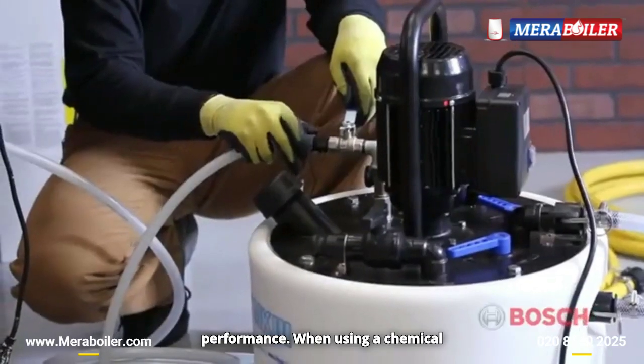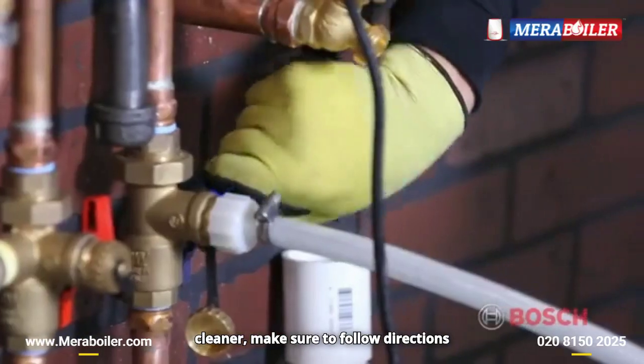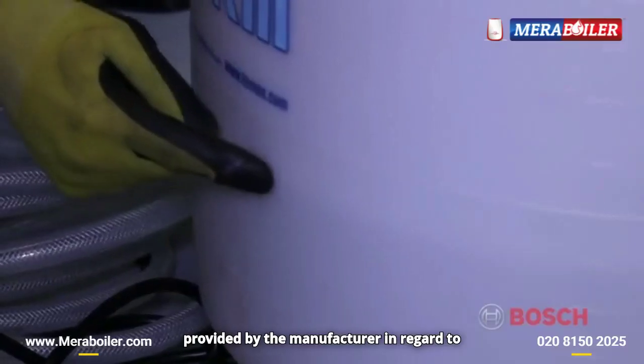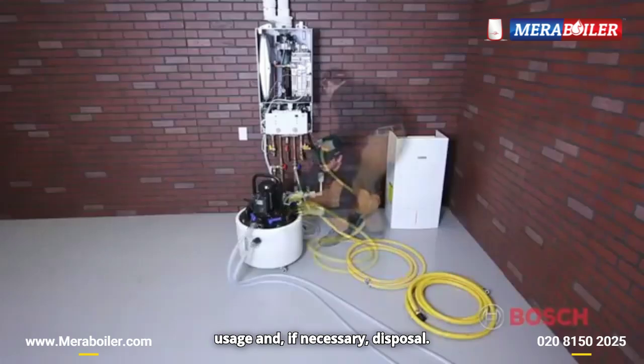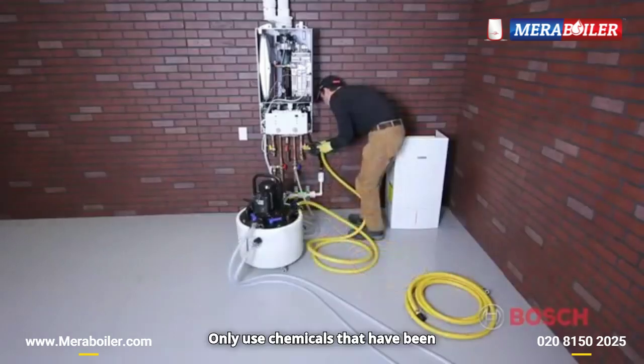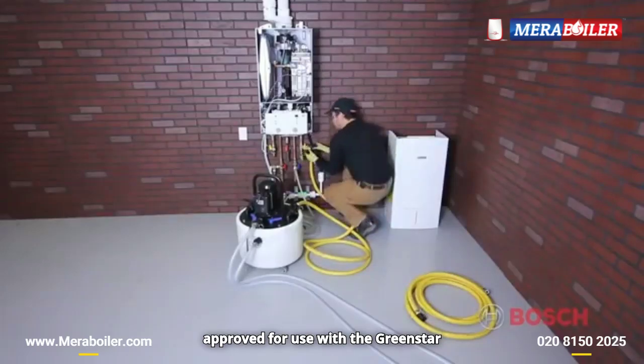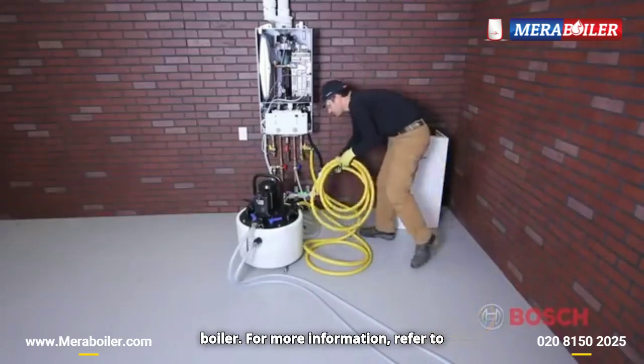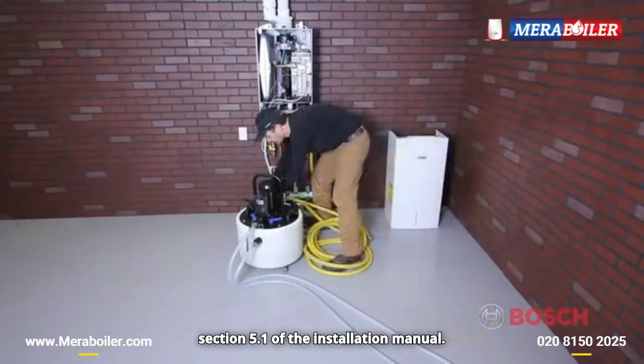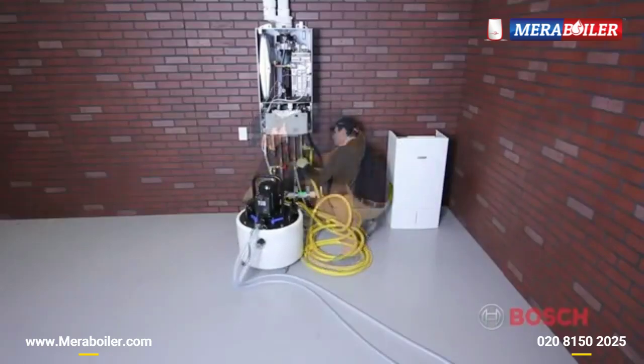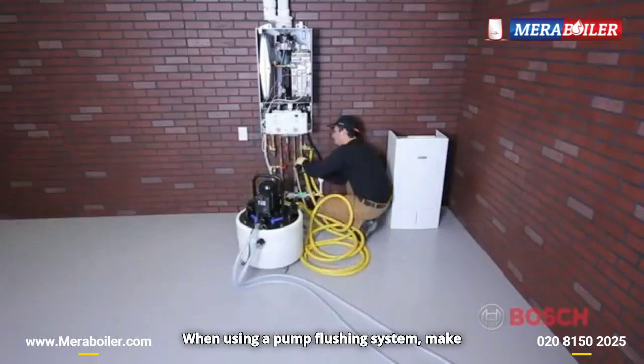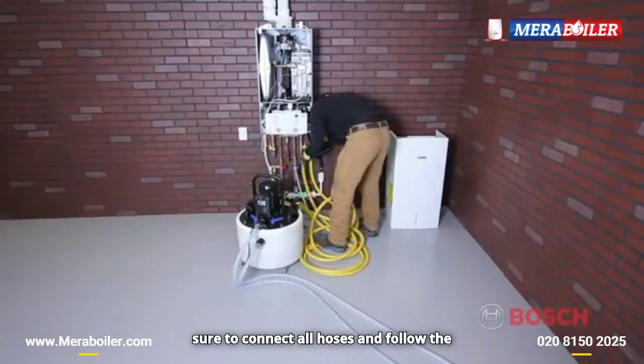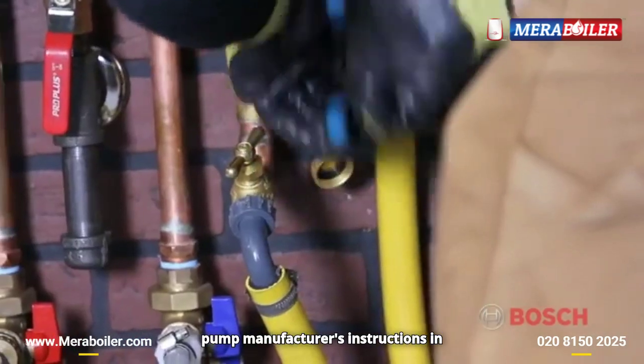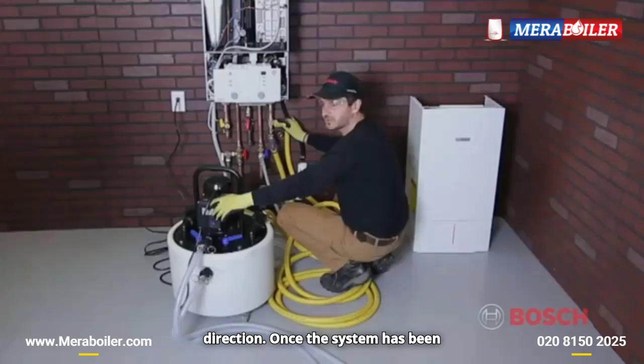When using a chemical cleaner, make sure to follow directions provided by the manufacturer in regard to usage and, if necessary, disposal. Only use chemicals that have been approved for use with the Greenstar boiler. For more information, refer to Section 5.1 of the installation manual. When using a pump flushing system, make sure to connect all hoses and follow the pump manufacturer's instructions in regards to fill levels and flow direction.